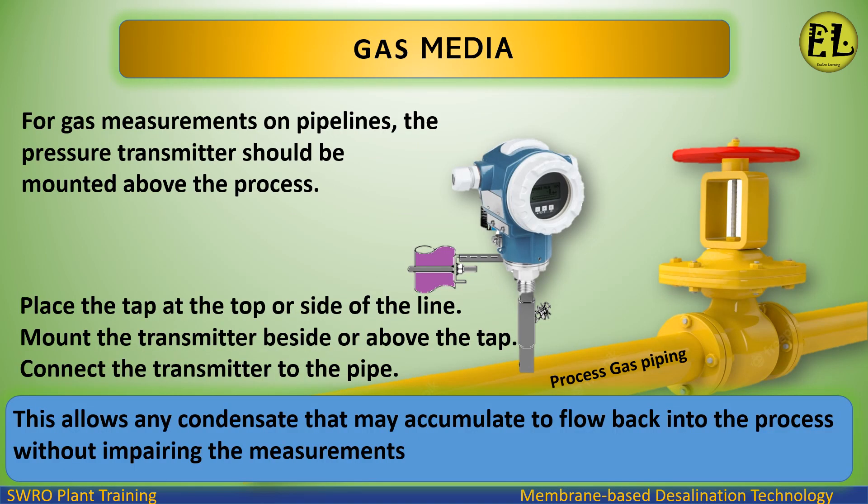Gas Media: For gas measurements on pipelines, the pressure transmitter should be mounted above the process. Place the tap at the top or side of the line, and mount the transmitter beside or above the tap, then connect the transmitter to the pipe. This allows any condensate that may accumulate to flow back into the process without impairing the measurements.